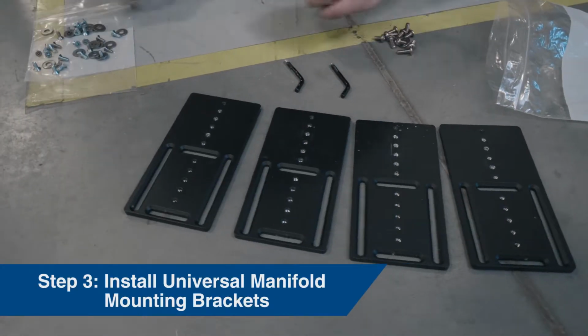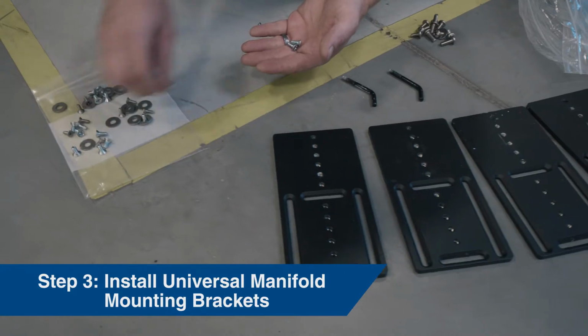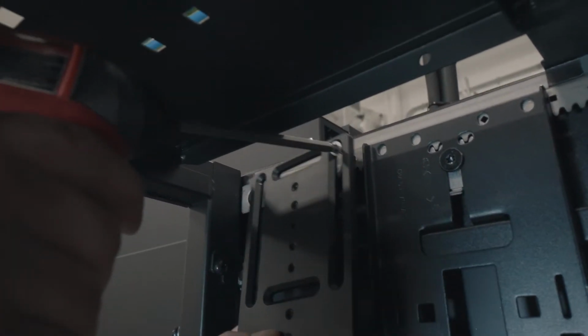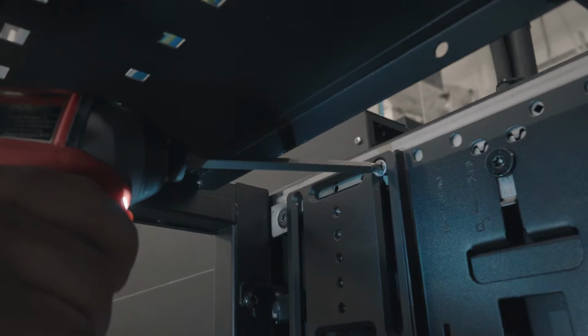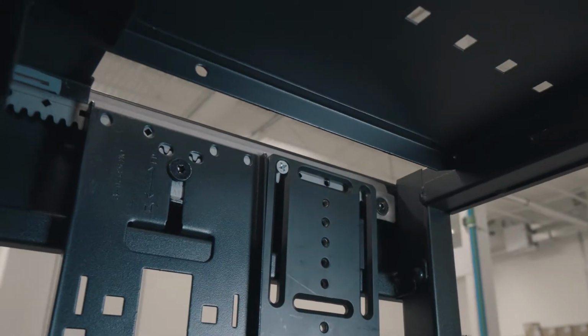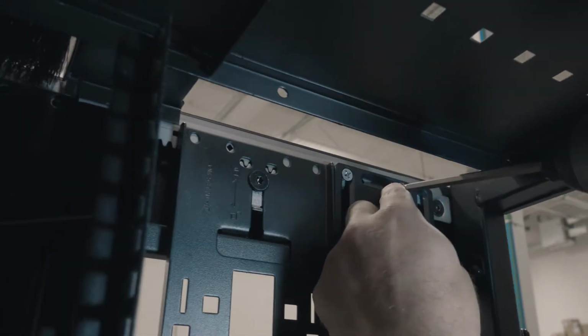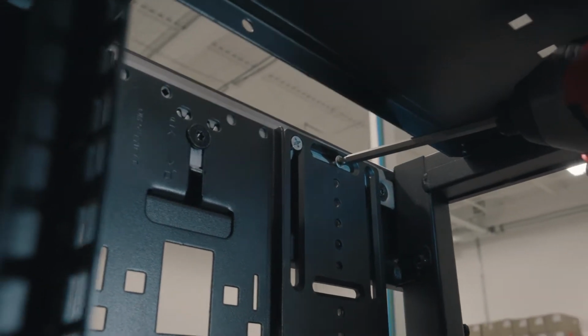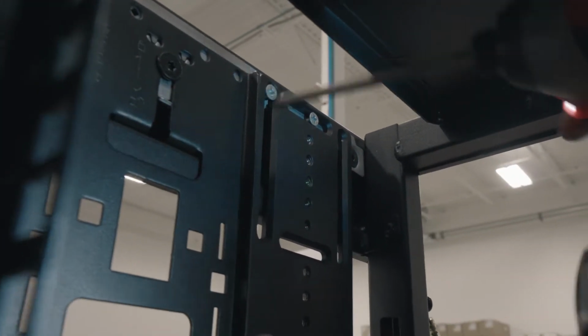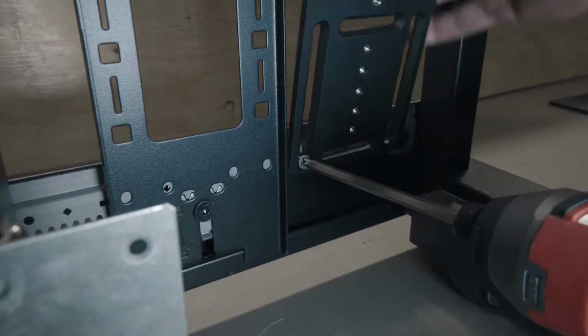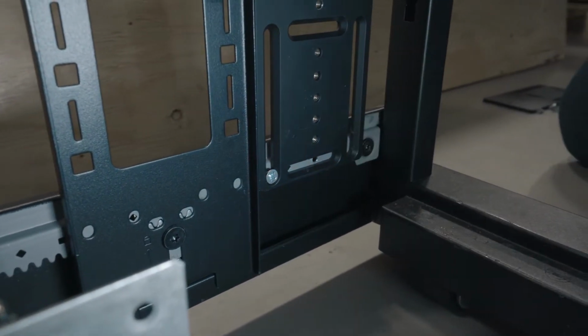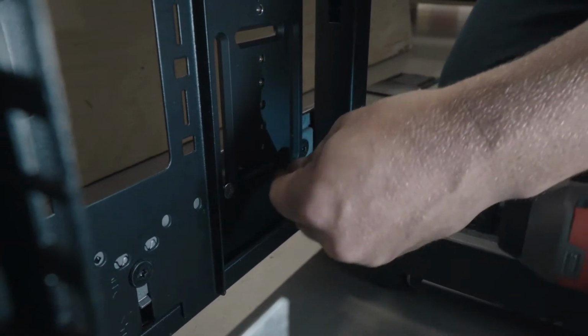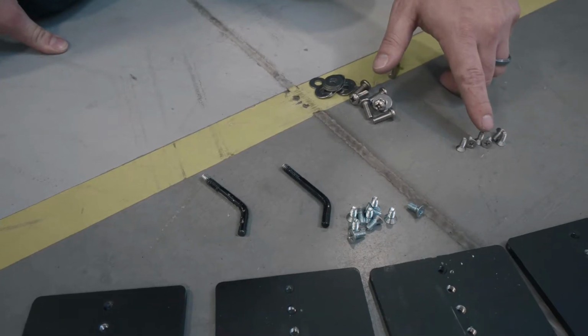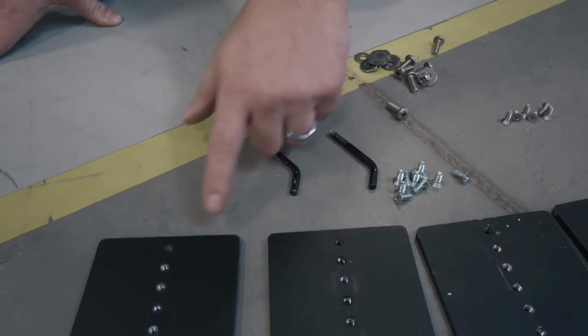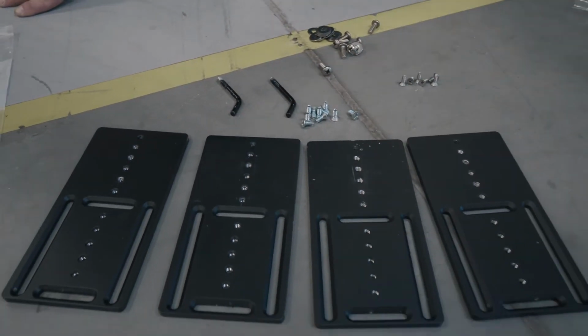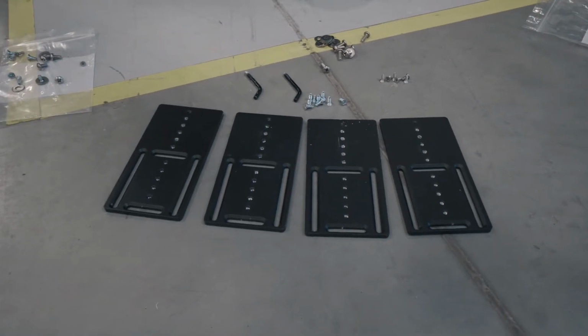Step 3. Install universal manifold mounting brackets. The manifold module requires the outermost PDU mounting location to be available for installation. Remove the PDU mounting bracket, as this is where the manifold module will be mounted. Remove the universal manifold mounting brackets from the crate and install into the rack so they match up to the mounting brackets on the manifolds, using the provided Phillips countersink self-threading screws. Choose the screws that best fit your rack, as 2 types have been provided. Your manufacturer's rack manual will show which screw size is required.